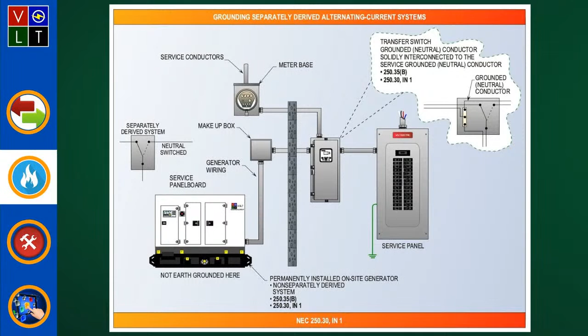Now this is where we're going to get into 250.30(A)(1) and (B). Basically, when you look at 250.30(A), that's where it talks about grounded systems, and it tells you that when you have a separately derived system, it's required to comply with certain headings that we're going to cover as we go through this: the system bonding jumper, the supply side bonding jumper, your grounded conductor, your grounding electrode, and also your grounding electrode conductor. We're going to discuss a single separately derived system, and also where we have multiple derived systems, and then get into the installation and bonding.